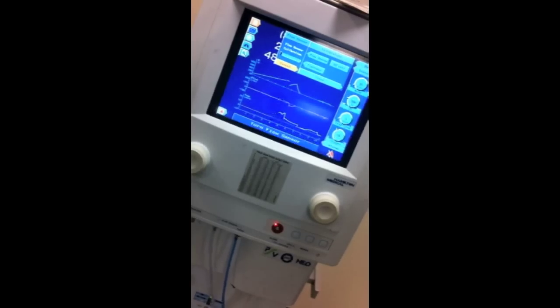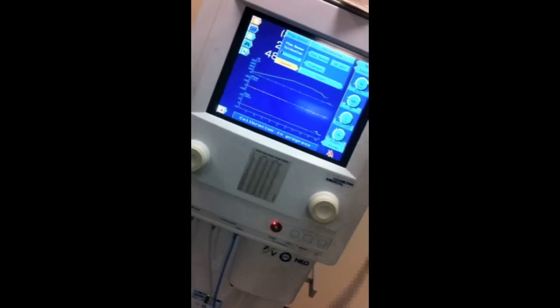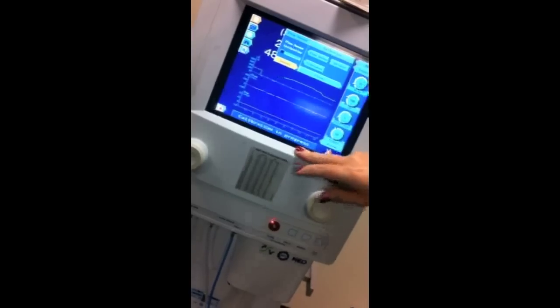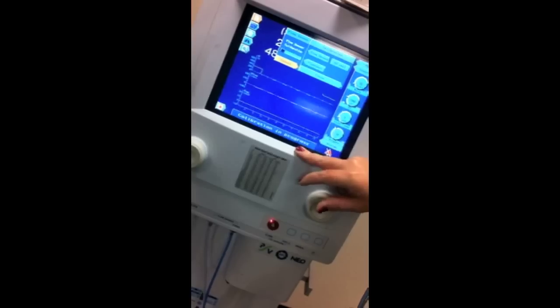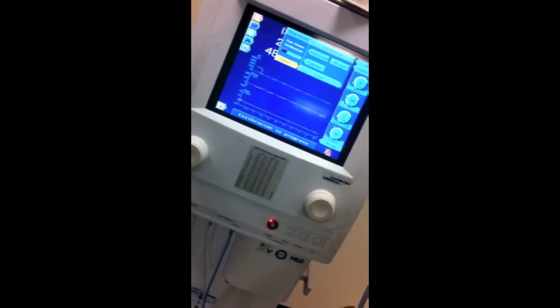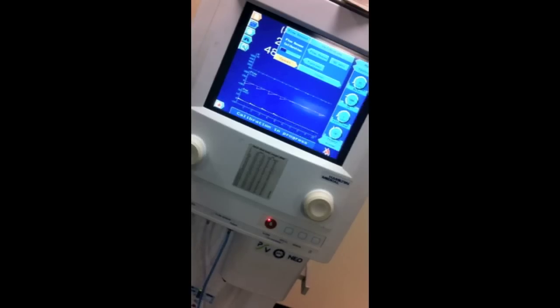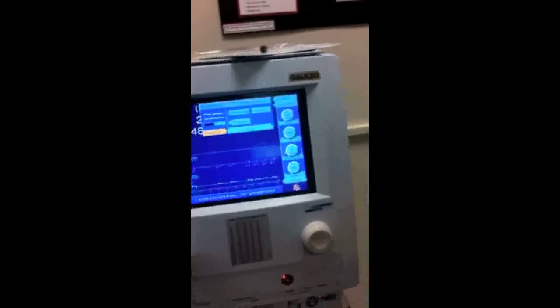When it asks to turn the flow sensor, you're literally taking it and turning it like that. So now it's upside down with the blue the other way. Okay? And then it knows I did that. It can sense it, so it's going to say calibration in progress. When you do this, if you watch your flow sensor, you'll see that it's increasing the flow, and it's sensing that by the sensor that's in there, and it can sense the changes.